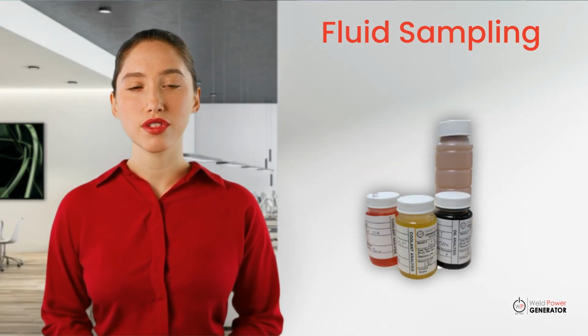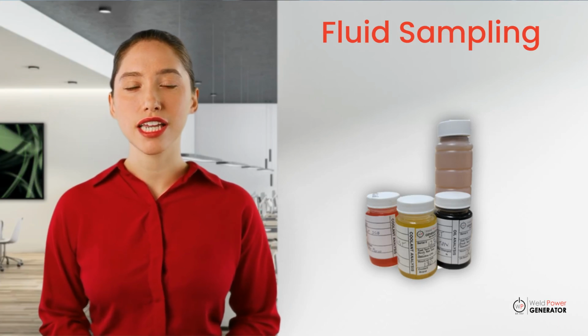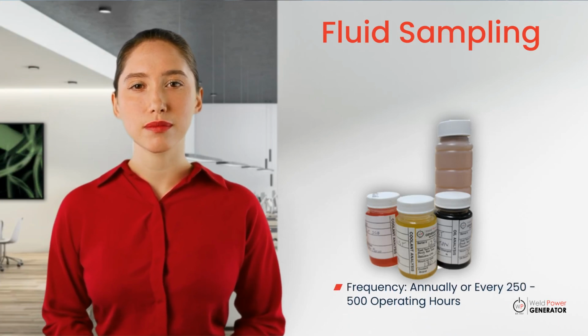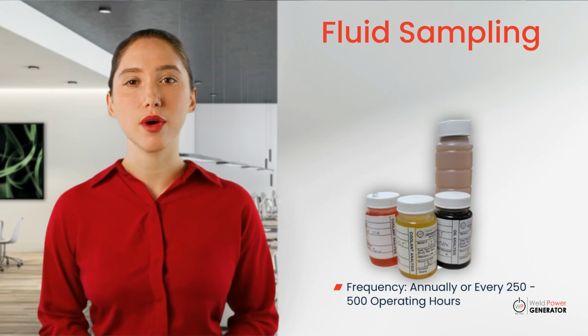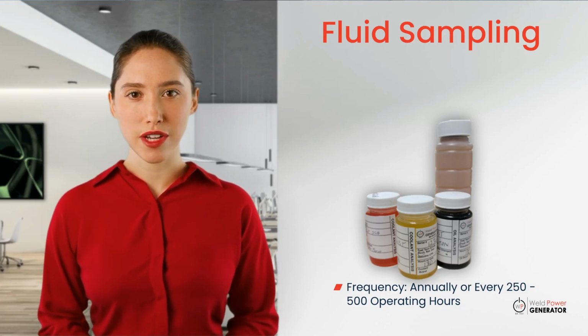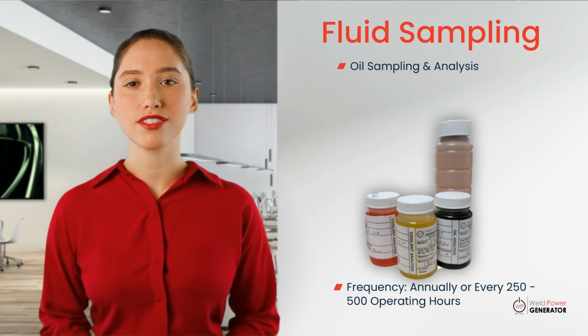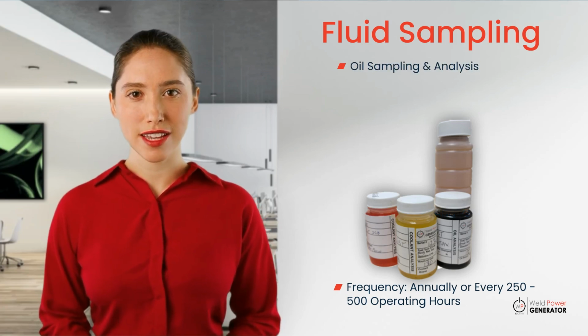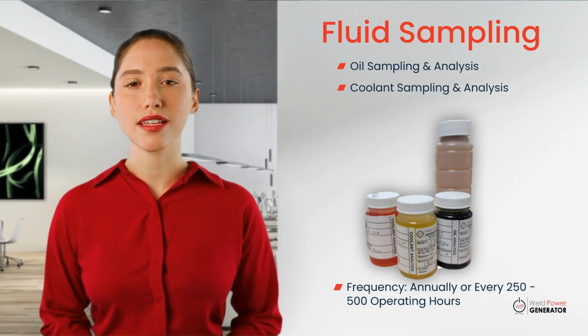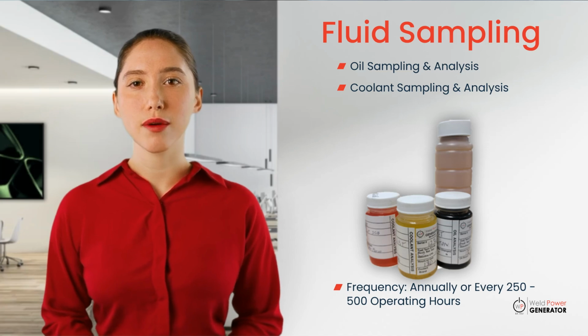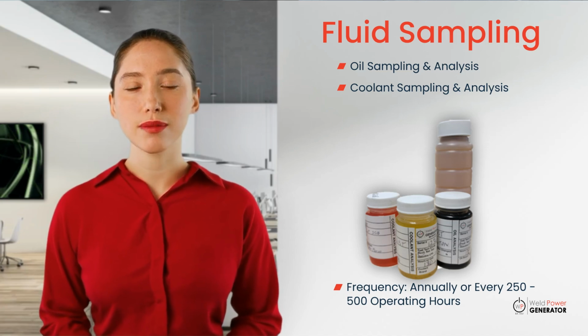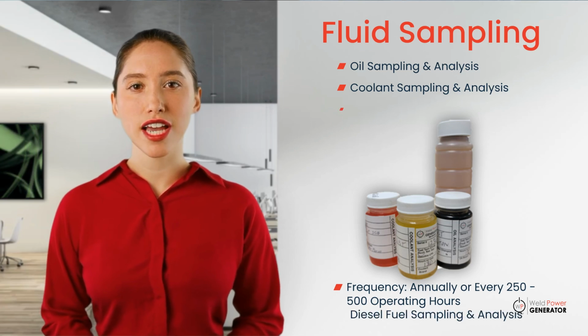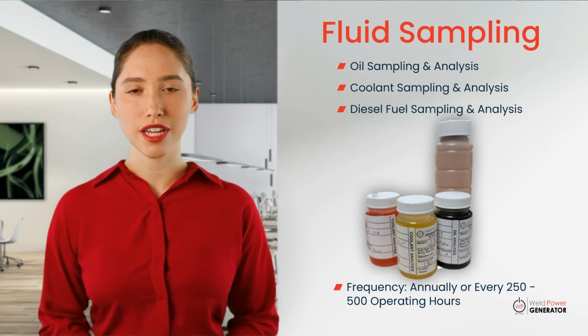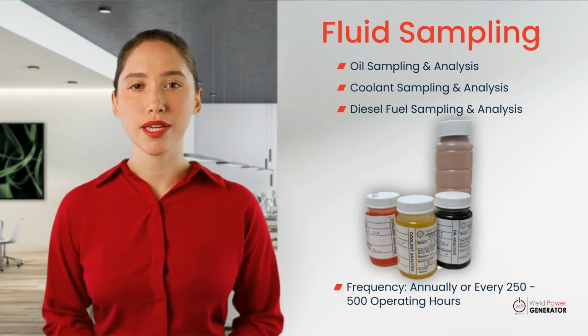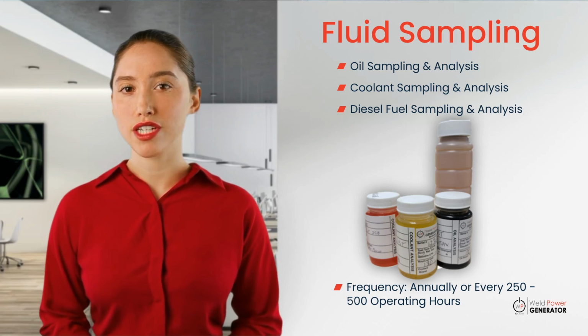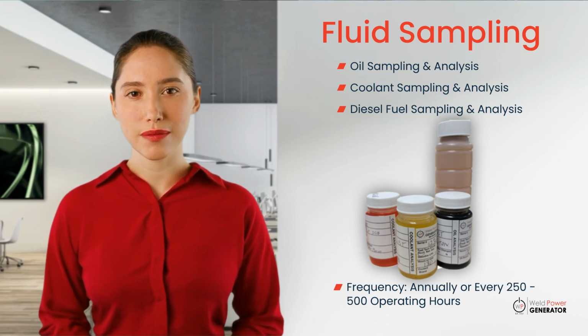Fluid sampling is essential for keeping your generator running smoothly and avoiding costly breakdowns. Fluid sampling should be conducted at least annually or after every 250 to 500 hours of generator operation. Oil sampling reveals early signs of engine wear, so you can address issues before they escalate. Coolant sampling checks the chemical balance, pH levels, and contaminants. This helps prevent corrosion and overheating, keeping the cooling system working efficiently. Finally, diesel fuel sampling is key to preventing generator failure. Annual testing catches contamination, water, and microbial growth, ensuring your generator's fuel stays clean and reliable.